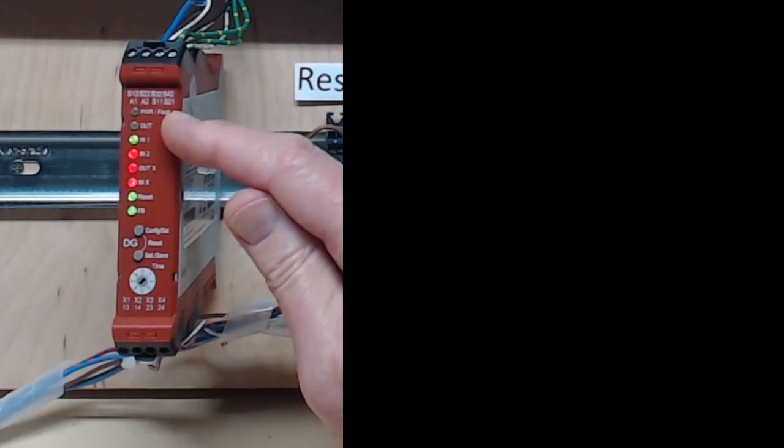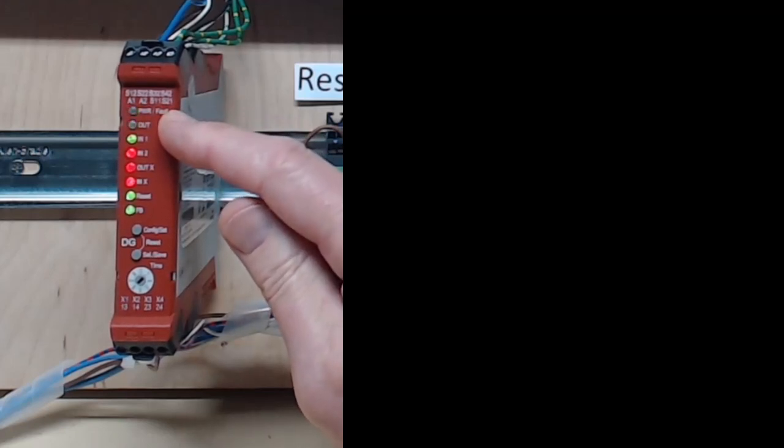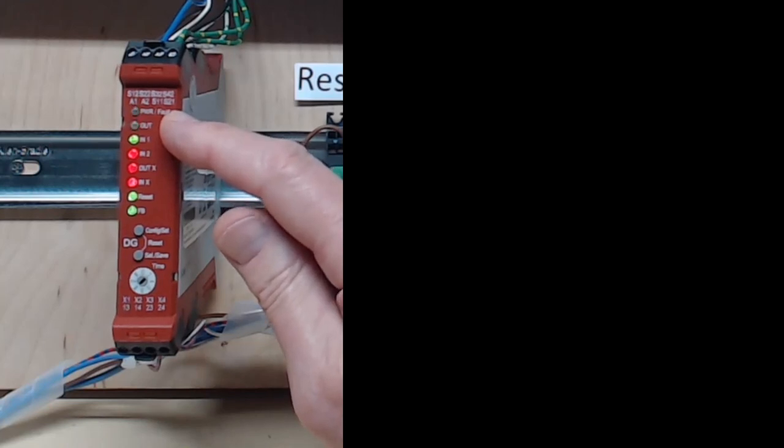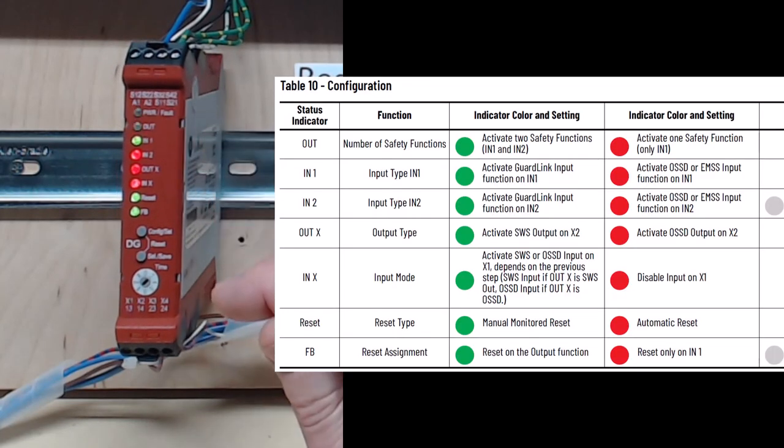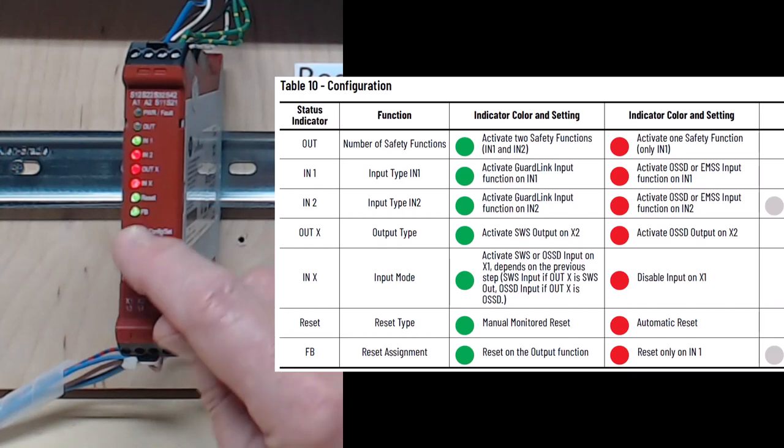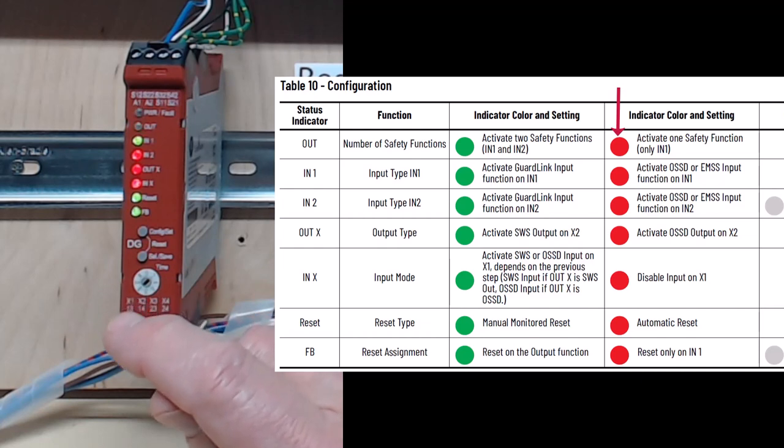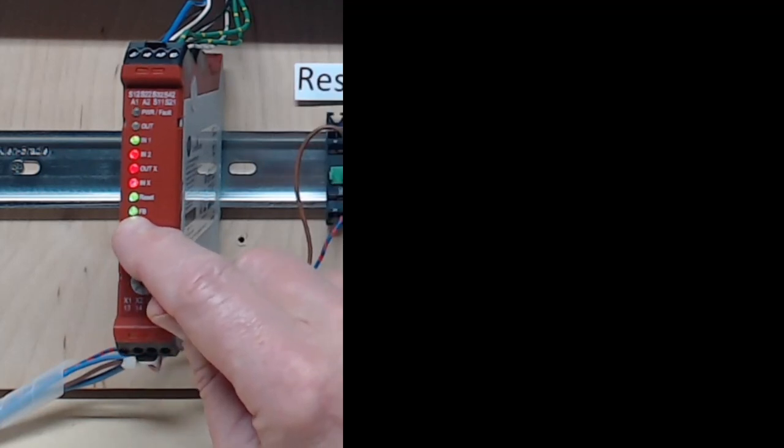You also see that the out LED is flashing green. The flashing indicates the feature that can be changed. Looking back at the configuration table, we see that the out LED will be green to activate two safety inputs, or you can press the config button to change it to red if you only wanted one safety input. Short press again to return it to green.